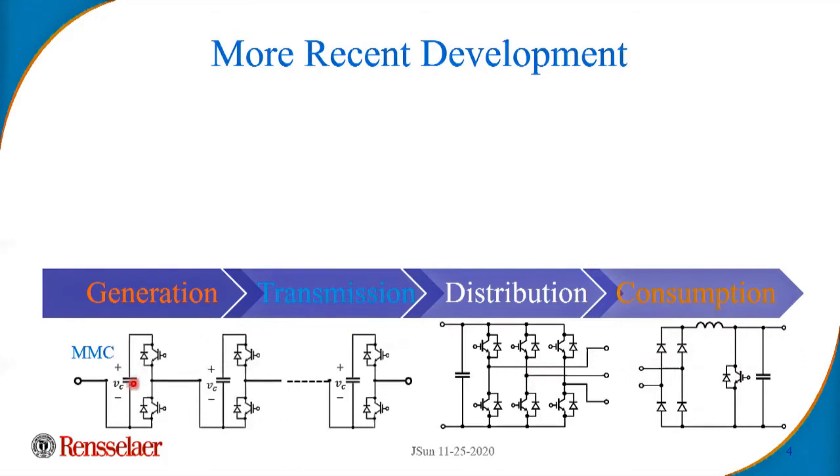The only major advancement, I think, from a practical standpoint, is the so-called MMC, modular multi-level converters, replacing the thyristor-based classical HVDC or STATCOM applications. So this is really taking over the high voltage, high power applications. This is a simplified diagram showing one phase leg of a modular multi-level converter. If you look at the new HVDC projects and STATCOM products that people are putting on the market, they're pretty much all based on MMC. So that's practically the most important development.